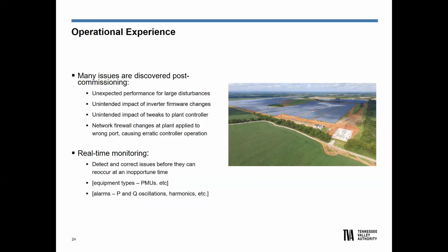There's also been a time that we had network firewall changes applied to a plant, not the correct one, the wrong one, causing erratic controller operations. So they got in the wrong plant remotely, applied network firewall changes to the wrong port, and caused erratic operation. Some things we've seen that have helped is real-time monitoring.